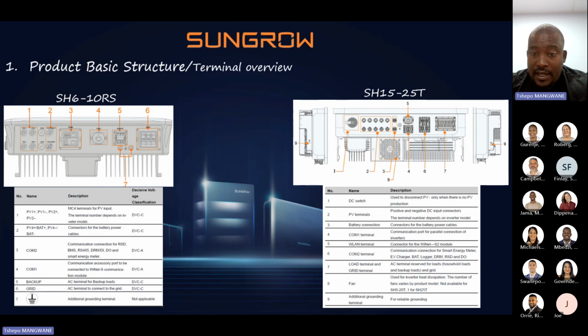7, it's our grid and load terminal. So the grid and load terminal in this form is different from the single phase side. If you look at the single phase side, they are separate. The backup terminal is separate from the input terminal. In this case, they're all built in one terminal port. But just know that on your right hand side, it's your main incomer. Then on your left hand side, it will be your load connection. Okay.